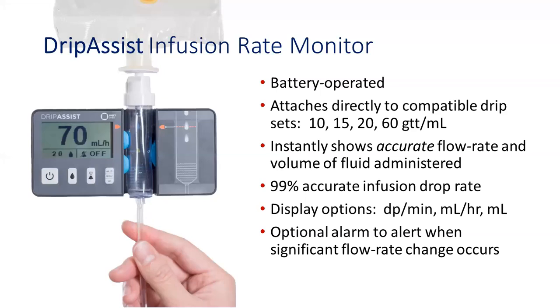And the way the device works is it has some infrared detectors that watch for drops, essentially. So as soon as you start an infusion, the device will immediately show you the flow rate information, and it will also show you the total volume of fluid that has been administered. And it will show the flow rate information in either milliliters per hour, as you see on the screen here. It can also show drops per minute. So depending on the kind of infusion that you're conducting. And let's see, so it runs off a 1 AA battery, works with any drip set.